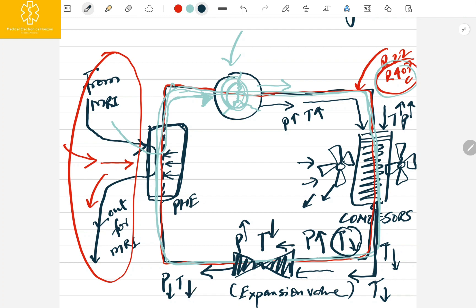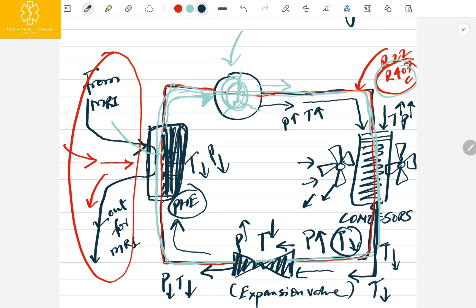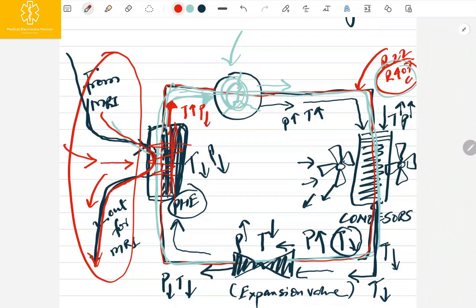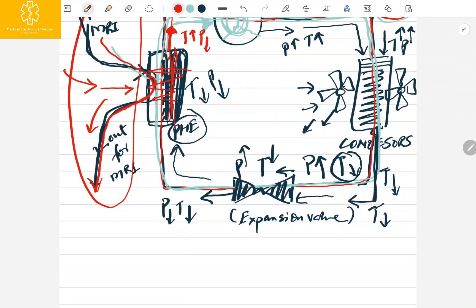Now we have a cold refrigerant with lower temperature and lower pressure entering the PHE. Here the refrigerant gas interacts with the water coming from the MRI, making that water cold, which then goes back to the MRI machine. After crossing the PHE, the gas has a slightly higher temperature and low pressure, so it goes back into the compressor again.